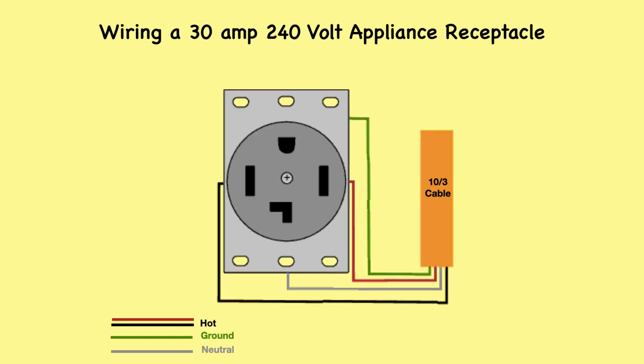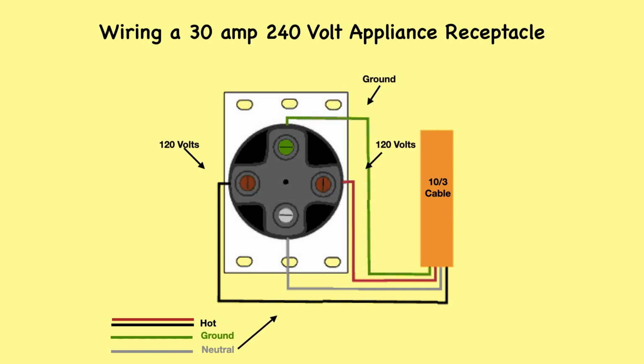This is a newer version of the outdated 30 amp receptacle appearing in the previous slide. This circuit is used for a new clothes dryer outlet installation. This receptacle has a ground connection not found in the older 30 amp circuit for added protection. A 30 amp outlet like this requires 10-3 cable with ground. The cable contains two 120 volt wires, a neutral wire, and a ground wire. This receptacle is connected to a dedicated 30 amp circuit breaker and provides a total of 240 volts to power the dryer heating elements, and 120 volts to power lights and other features of the appliance.